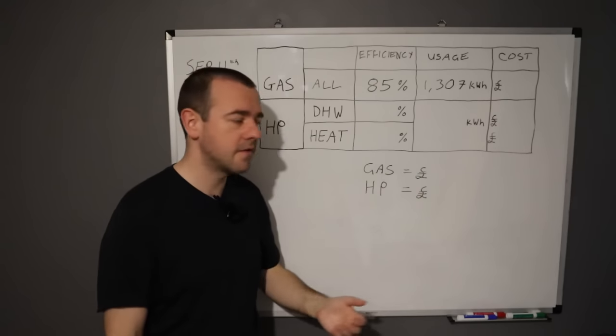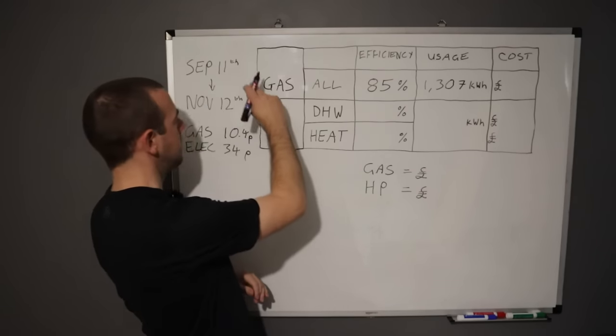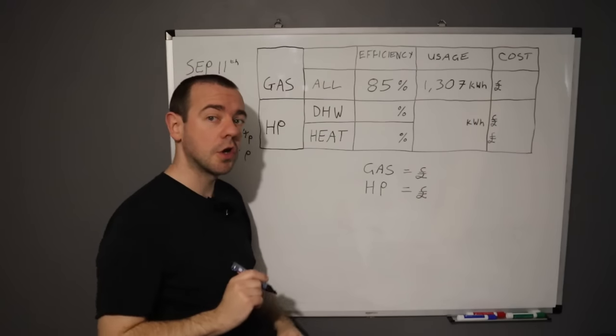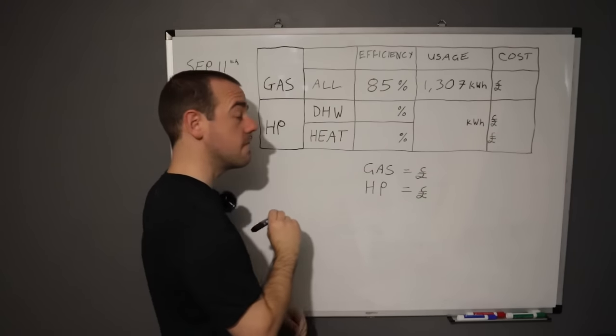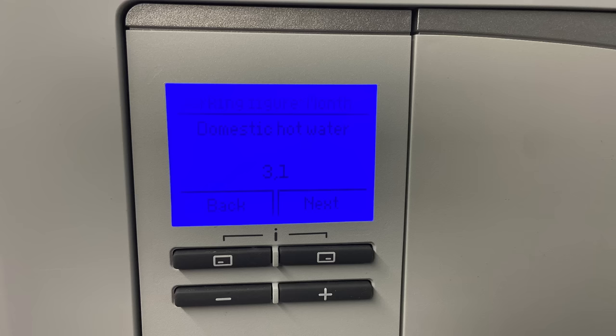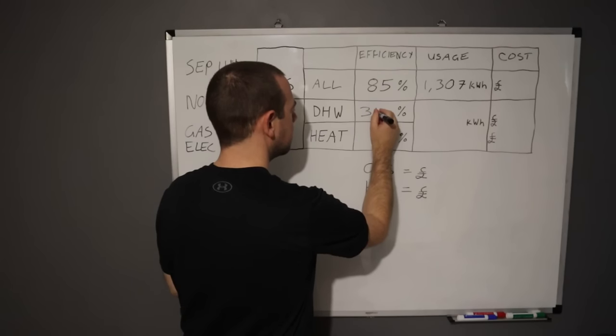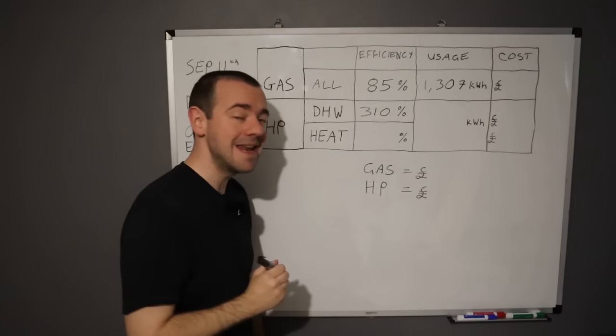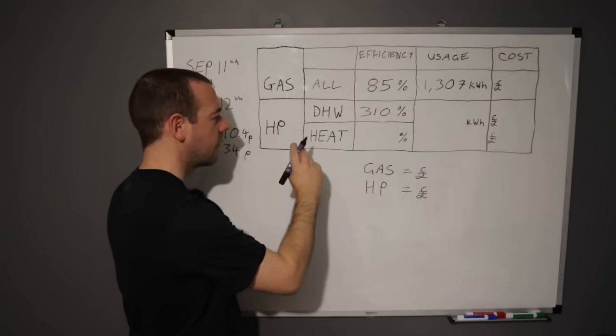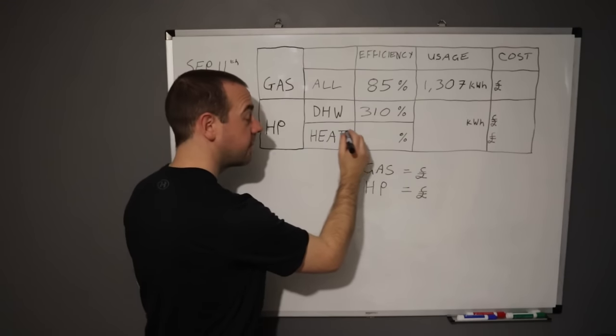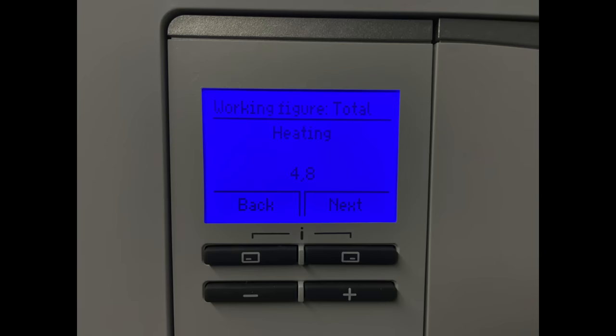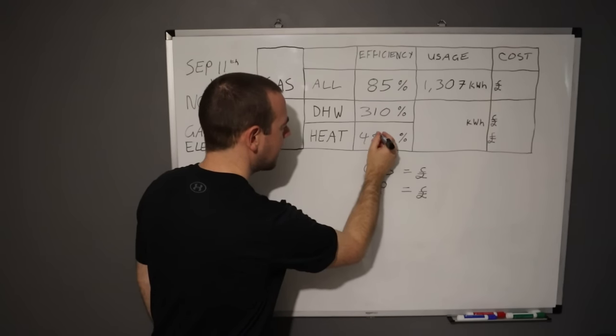Legionella is taken care of with cycles. That sees us through the day until it heats up again the following day. So far in this two month period we have got a COP for hot water of 3.1 or as I prefer to say it, 310% efficient. For heating we have got a COP of 4.8 or 480% efficient.